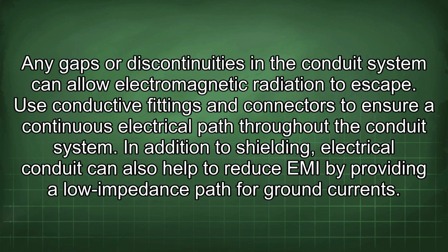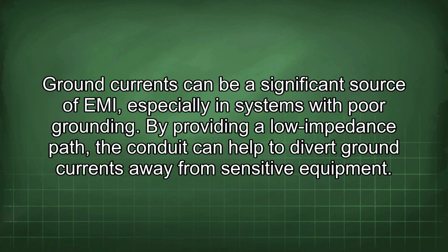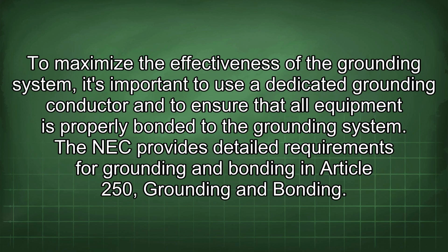In addition to shielding, electrical conduit can also help to reduce EMI by providing a low impedance path for ground currents. Ground currents can be a significant source of EMI, especially in systems with poor grounding. By providing a low impedance path, the conduit can help to divert ground currents away from sensitive equipment. To maximize the effectiveness of the grounding system, it's important to use a dedicated grounding conductor and to ensure that all equipment is properly bonded to the grounding system. The NEC provides detailed requirements for grounding and bonding in Article 250, Grounding and Bonding.